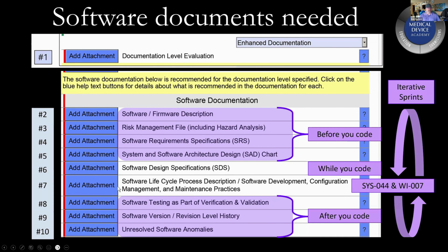So you don't have to comply with 62304. You can invent a new way to document software. Go ahead, but it's got to meet all the requirements that are in 62304, whether you comply with it or not. So good luck. Why would you bother creating a new method when you can just copy somebody else's? Same thing goes for the cybersecurity.